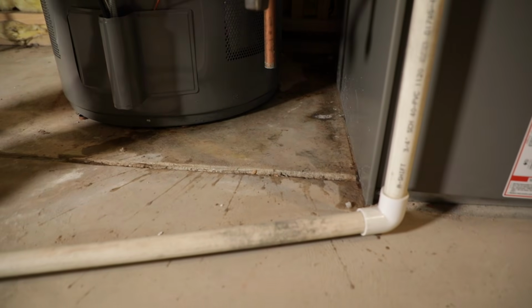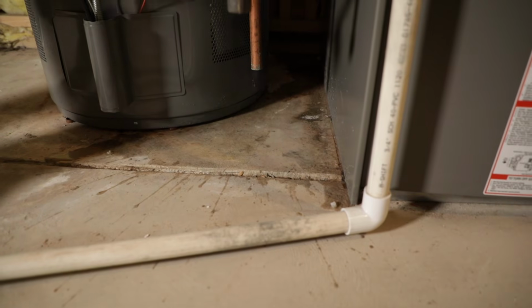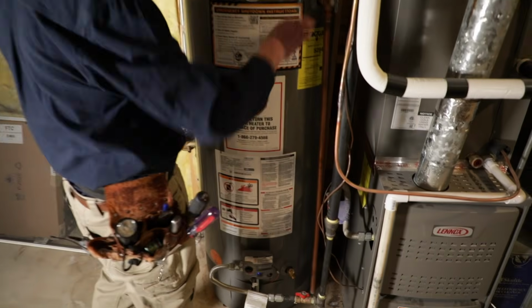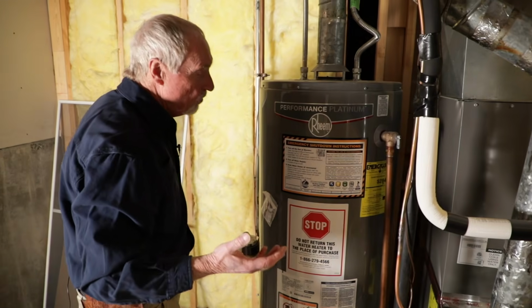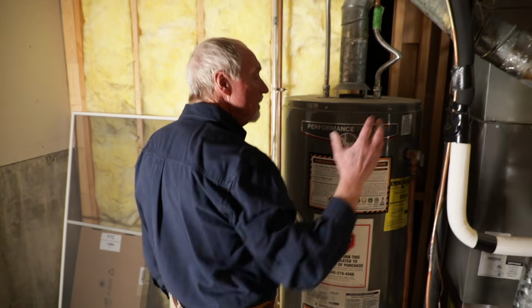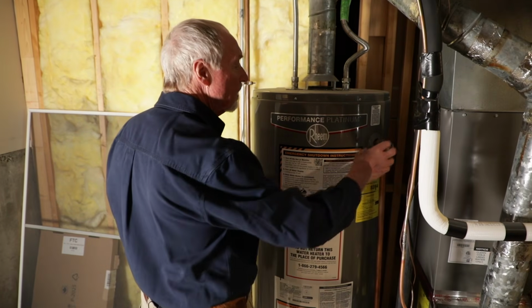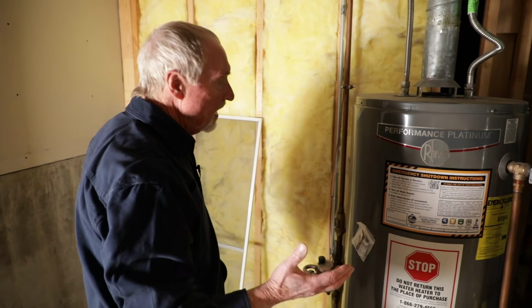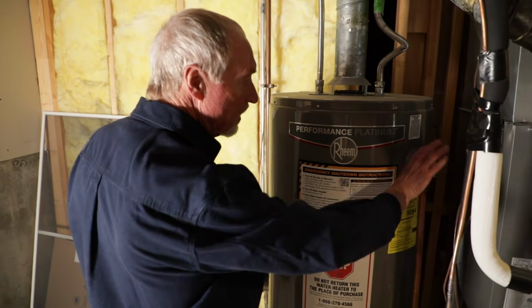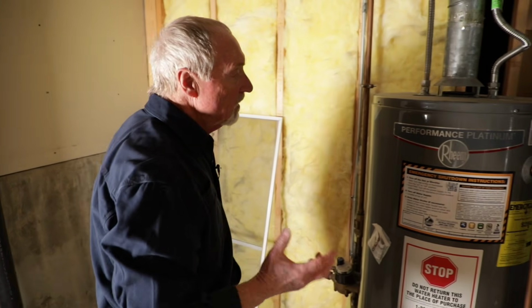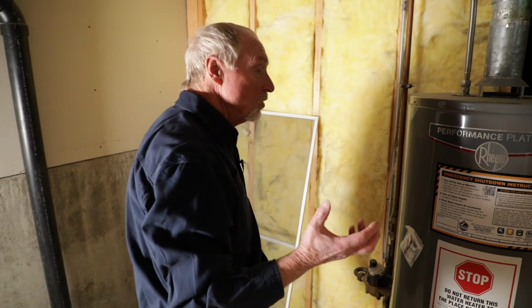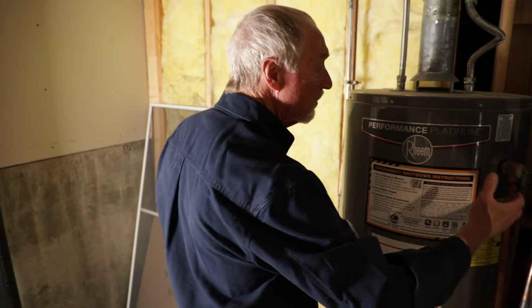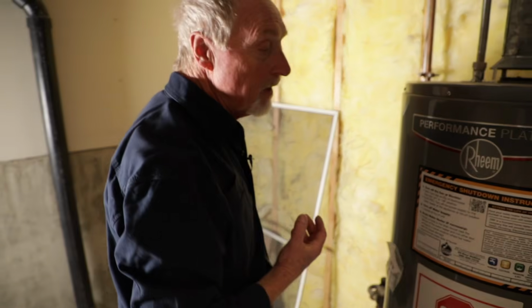And there we see it piddling out. So this one is operating the way it should. This is one of these places where you know what you're comfortable doing. If you're comfortable doing this, great. If not, that's fine. You just observe the condition of the valve, no unusual mineral buildup around it, rust, corrosion, anything like that.